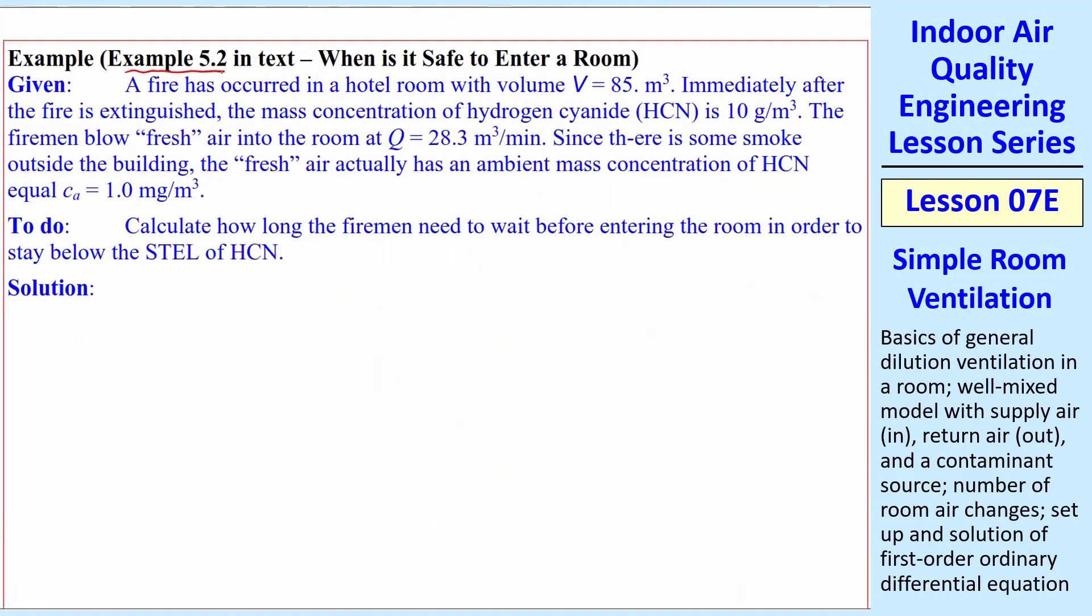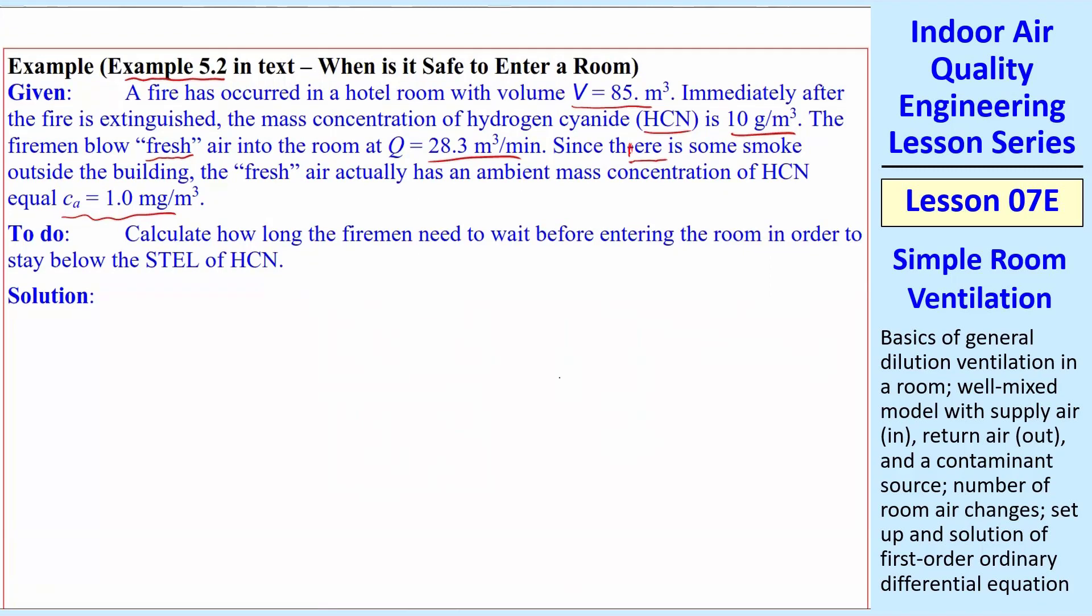Time for an example. A fire has occurred in a hotel room. Here's the volume of the room. And immediately after the fire is extinguished, we have some hydrogen cyanide, HCN, in the room. Its mass concentration is 10 gram per meter cubed. So they were burning some nasty stuff there. Firemen blow fresh air into the room at a certain volume flow rate. So this is the supply coming in. The fresh air actually has some ambient concentration, and we're going to say that's 1.0 milligram per meter cubed. But inside, it's 10 grams per meter cubed. Calculate how long the firemen need to wait before entering the room in order to stay below the STEL. Short-term exposure limit is appropriate because you don't have the firefighters fighting that fire for eight hours a day, 40 hours a week. The firemen will probably be in the room no more than 15 minutes. Remember, this STEL is based on 15 minutes. The STEL is equal to 5 milligram per meter cubed. That means that a fireman can tolerate that for 15 minutes at 5 milligram per meter cubed.